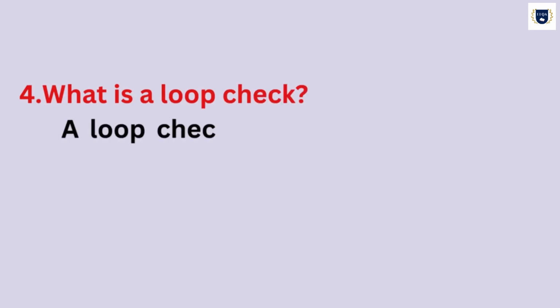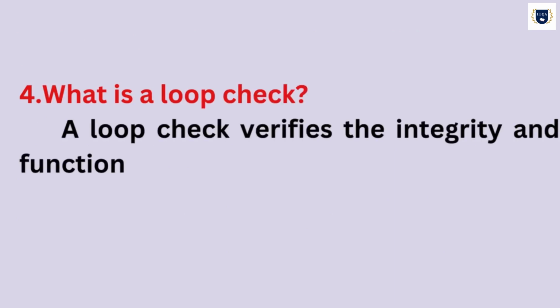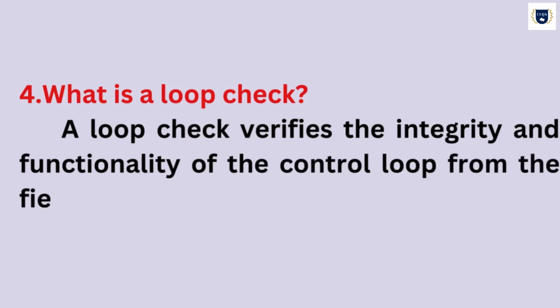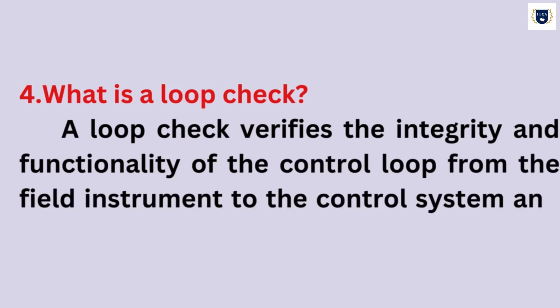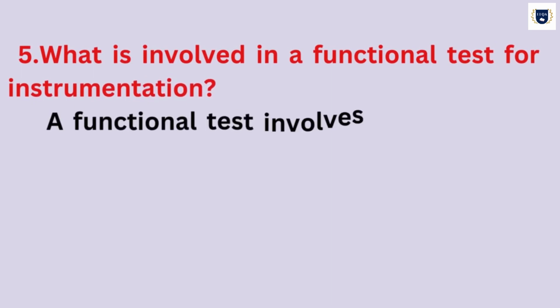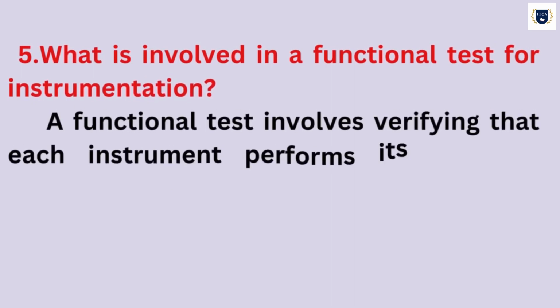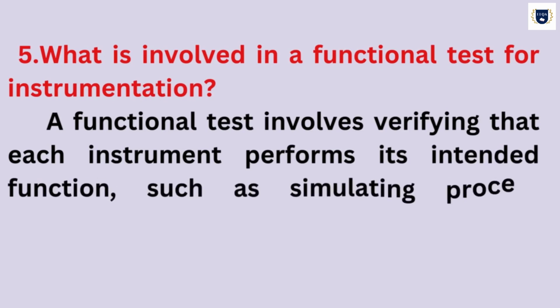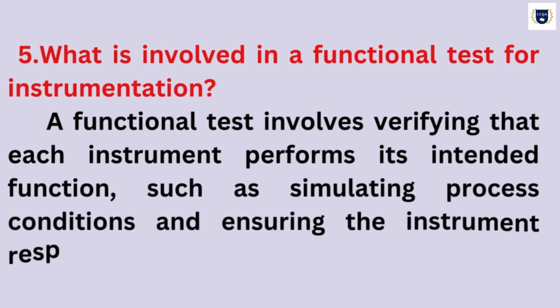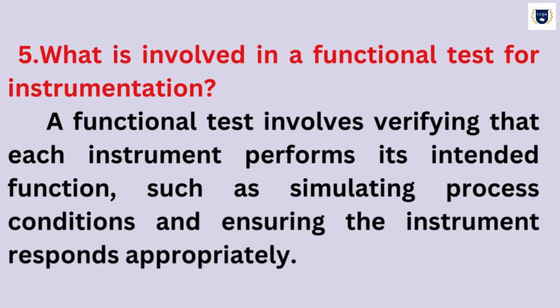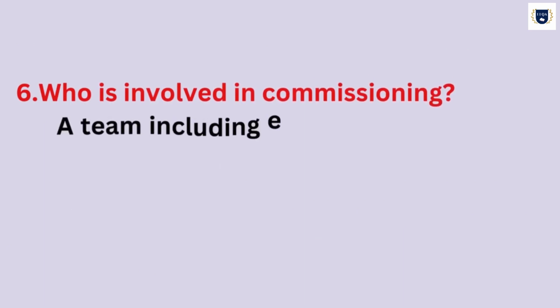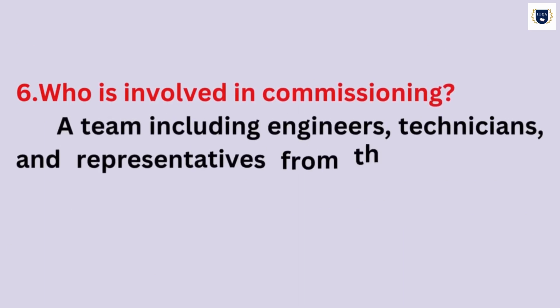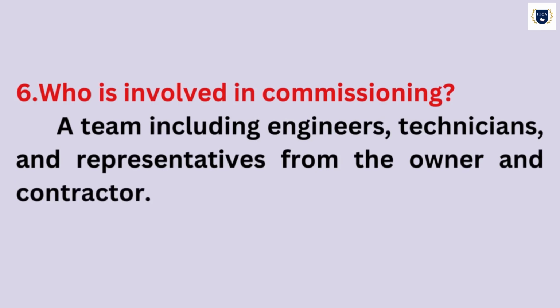What is a loop check? A loop check verifies the integrity and functionality of the control loop from the field instrument to the control system and back. What is involved in a functional test for instrumentation? A functional test involves verifying that each instrument performs its intended function, such as simulating process conditions and ensuring the instrument responds appropriately. Who is involved in commissioning? A team including engineers, technicians, and representatives from the owner and contractor.